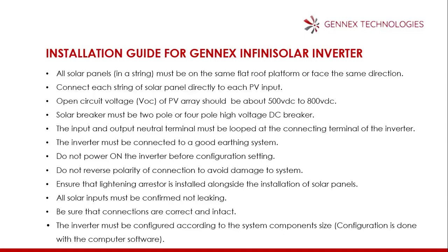Do not power on the inverter before configuration setting. Which means once you connect the solar input, you power only the solar input after the battery is switched on, so that you can do your configuration before you proceed. Do not reverse polarity of connection to avoid damage to the system.